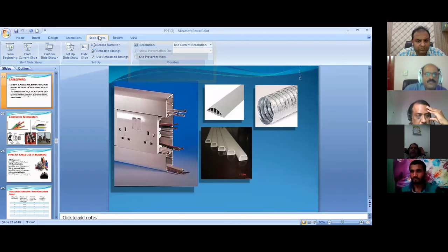So a cable is a length of single conductor having several wires stranded together. That means one copper conductor is stranded into different strands. If you take a 1 square mm cable, it has got 14 strands of 0.3 mm. We call it 14/0.3. 14/0.3 is 14 wire strands of 0.3 mm stranded together, and over and above it is insulated. So that is how the cable is made: two or more conductors, each provided with its own insulation and laid up together. The insulated conductor may or may not be provided with an overall protective covering.